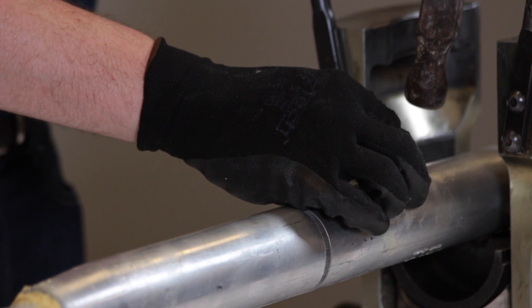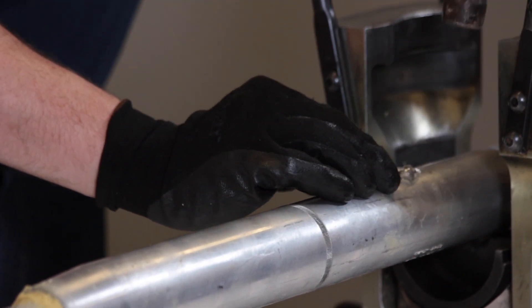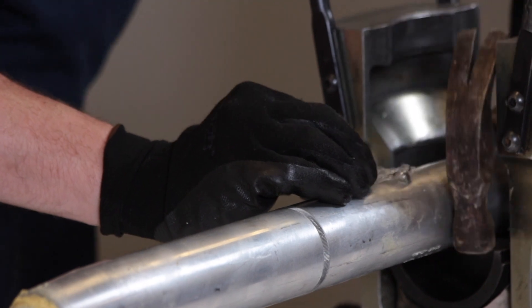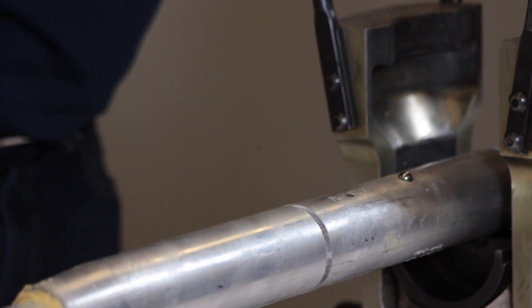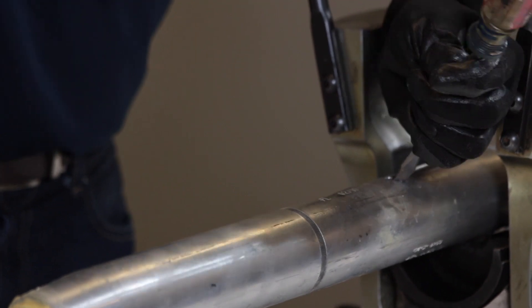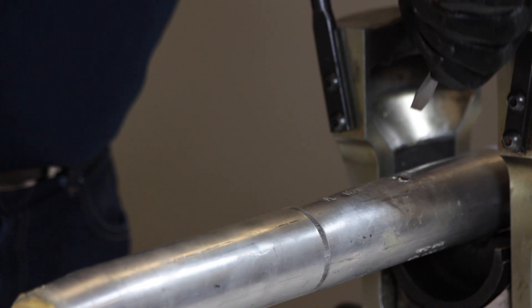Seal the filler hole by inserting the stainless steel ball. The plastic bag containing the ball can be used to help position it. Tap the ball into the filler hole using a hammer and remove the plastic bag if used. Next, peen over the aluminum edges of the filler hole with a hammer and flathead screwdriver to secure the ball into place.